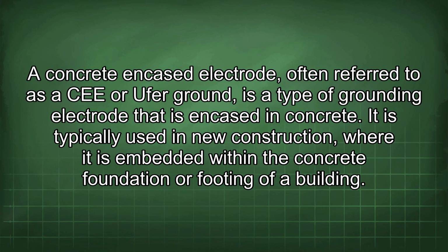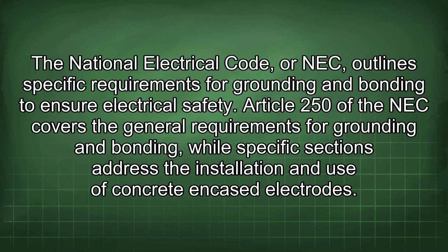A concrete encased electrode, often referred to as a CEE or Ufer ground, is a type of grounding electrode that is encased in concrete. It is typically used in new construction, where it is embedded within the concrete foundation or footing of a building. The National Electrical Code, or NEC, outlines specific requirements for grounding and bonding to ensure electrical safety. Article 250 of the NEC covers the general requirements for grounding and bonding, while specific sections address the installation and use of concrete encased electrodes.